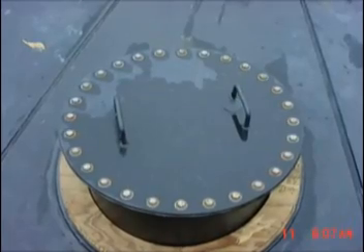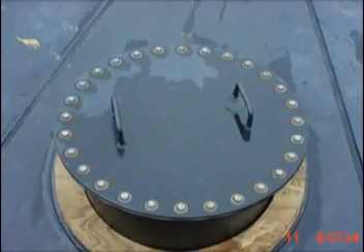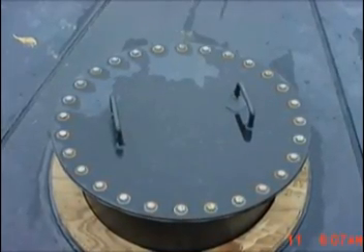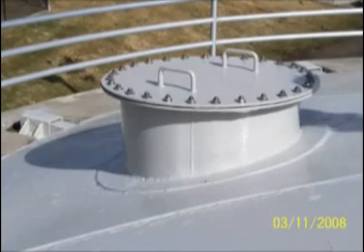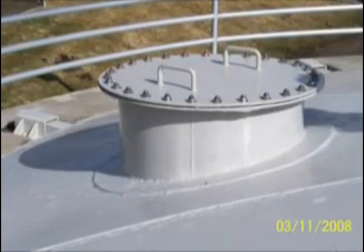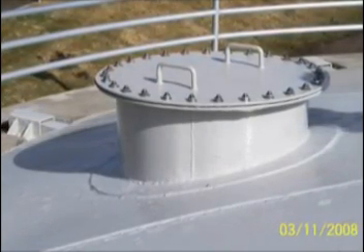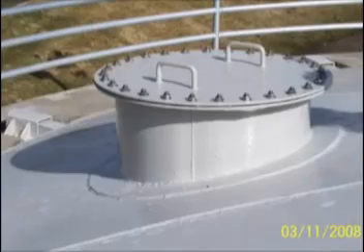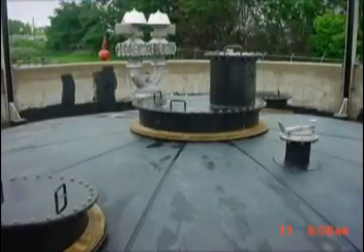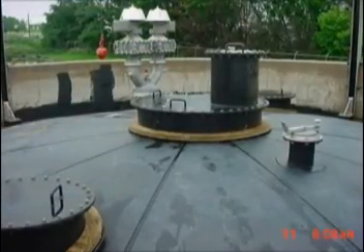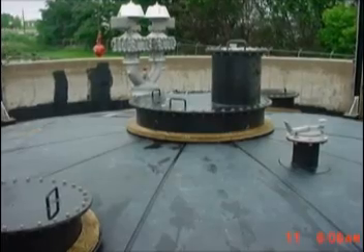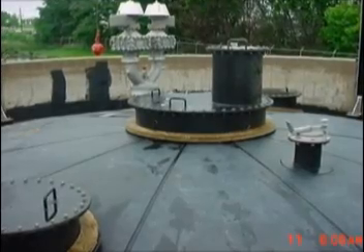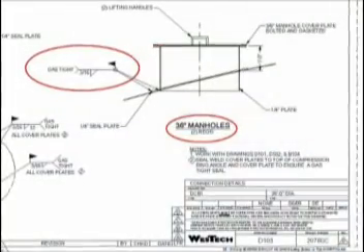Position and weld the adapter rings. Use gas-tight welds. Install cover plates, manhole covers, and spark-resistant quick-opening sample tube hatches. Be sure to include the gaskets and to tighten the bolts evenly. Apply anti-seize to all stainless steel bolts.